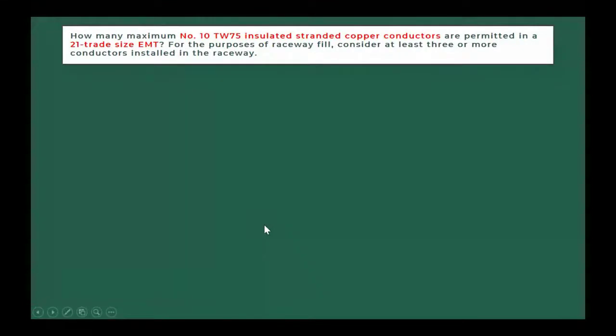How many maximum? Okay, here we go. This is the one I was telling you about that's probably the hardest one to do. So this question is asking, how many number 10s maximum stranded copper conductors are permitted in a 21 trade size EMT? For the purposes of raceway fill, let's consider that there's got to be at least 3 or more conductors installed in the raceway.